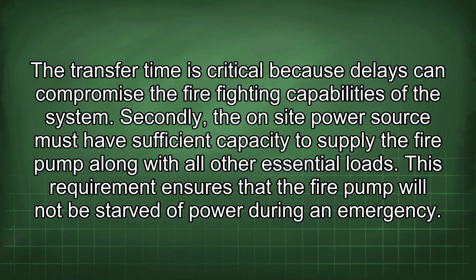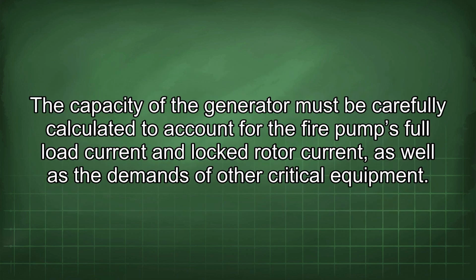Secondly, the on-site power source must have sufficient capacity to supply the fire pump along with all other essential loads. This requirement ensures that the fire pump will not be starved of power during an emergency. The capacity of the generator must be carefully calculated to account for the fire pump's full load current and locked rotor current, as well as the demands of other critical equipment.